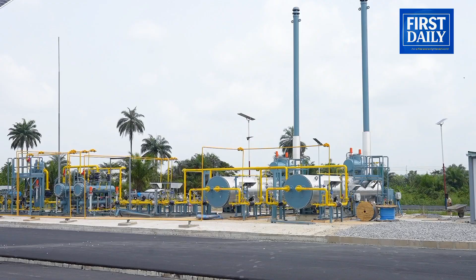We did about 400 meters of 6-inch gas pipeline to this point, where the gas is processed to allow the gas intake of the system to be regulated. The pressure coming in from the pipeline is about 80 bars, but these machines run at a maximum of 20 bars, so you need to bring it into a system that regulates the pressure for the power plants to take in. Anything above 20 bars will trip the machines.